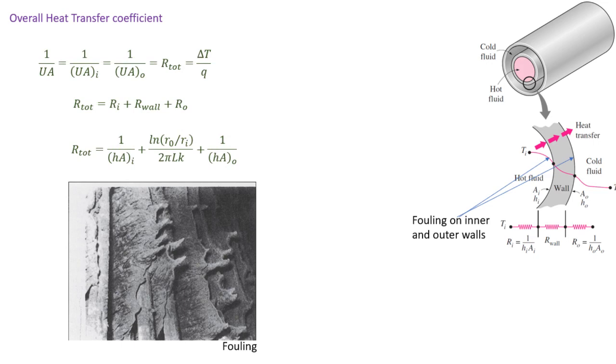Another thing we need to be concerned about is fouling. So the performance of heat exchangers will deteriorate over time as the result of an accumulation of deposits on those heat transfer surfaces. Those deposits, which can happen on the hot side and the cold side, increase the thermal resistance and have to be accounted for.